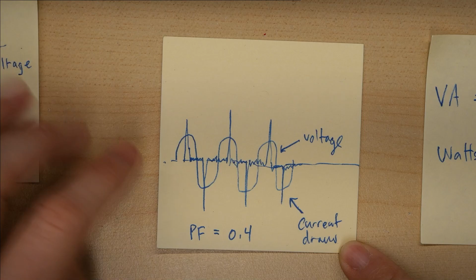I've drawn an example of the current draw, which doesn't represent anything in particular. I've written down a power factor of 0.4. Notice how these spikes don't follow the waveform, they just shoot up and then head back down. The transformer has to handle these current spikes, which can go far in excess of the average current draw you might be measuring.